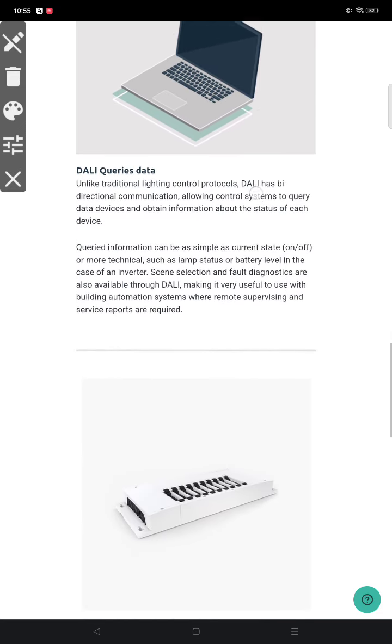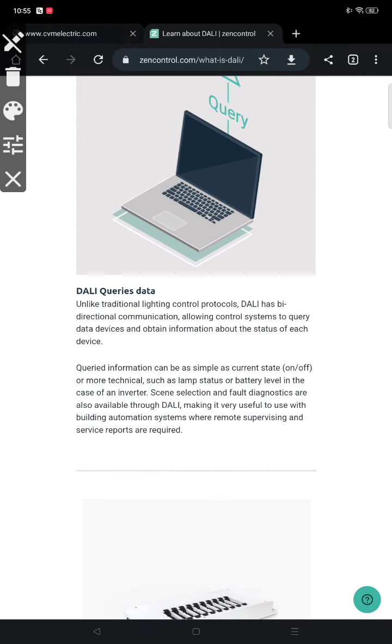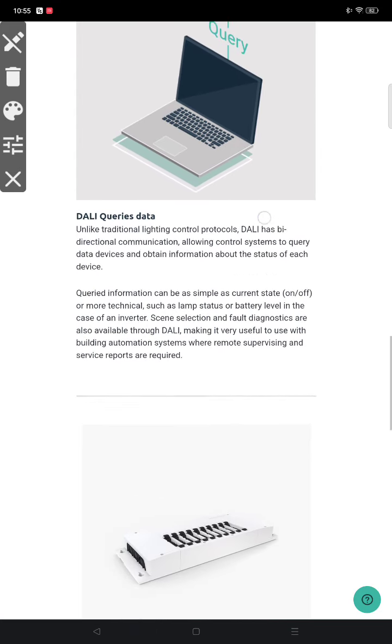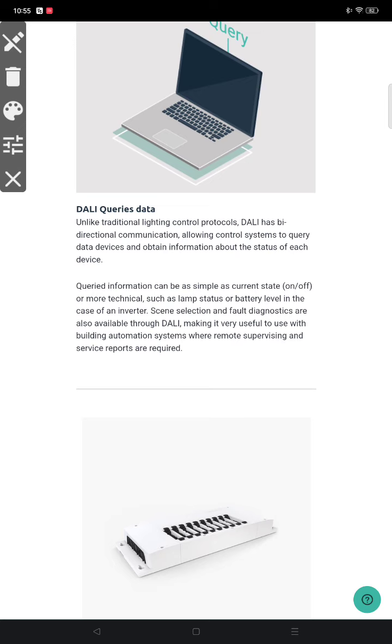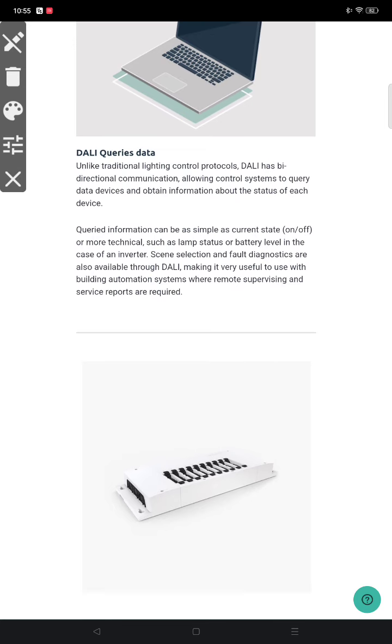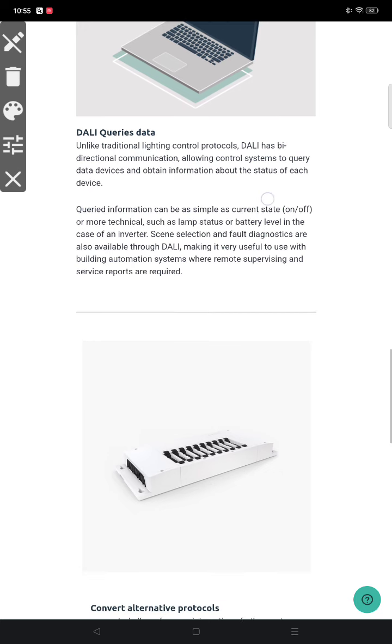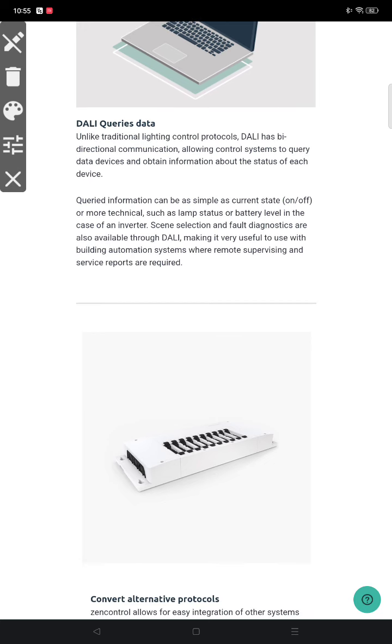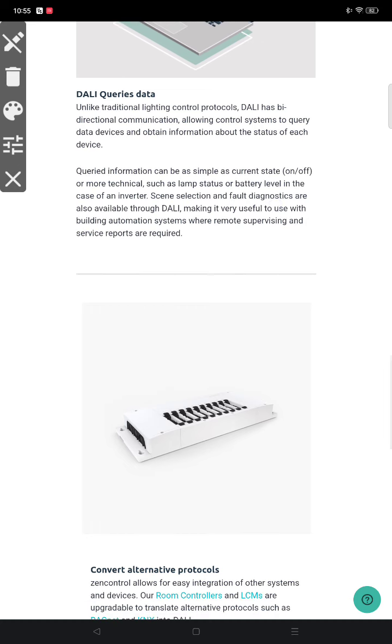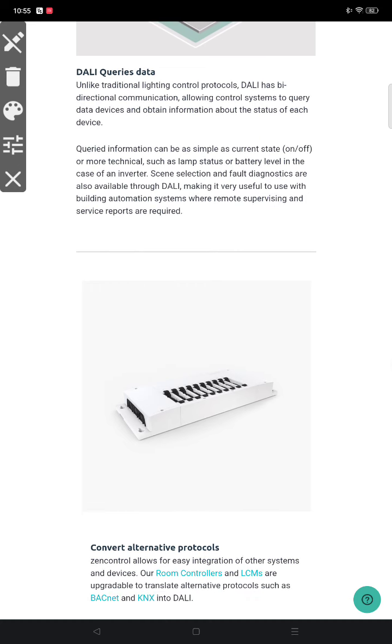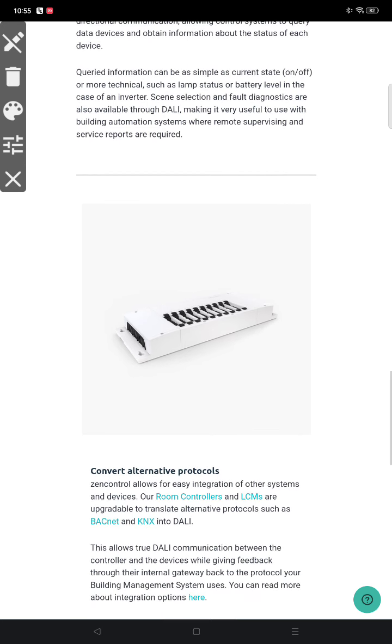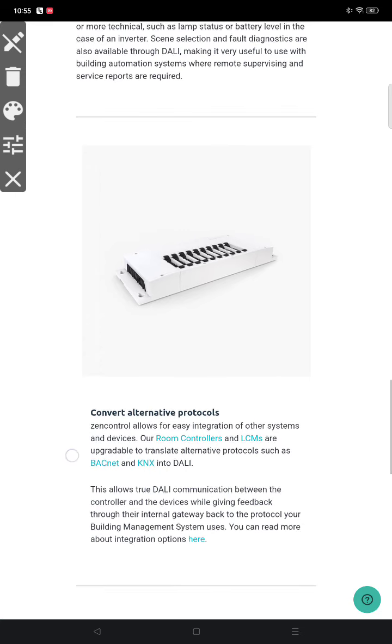DALI queries data. Unlike traditional lighting control protocols, DALI has bidirectional communication that allows control systems to query data from a device and obtain information about the status of each device. Query information can be as simple as the current state, on or off, or more technical, such as lamp status or battery level in the case of inverters. Scene selection and fault diagnostics are also available through DALI, making it very useful with building automation systems where remote supervising and service reports are required.